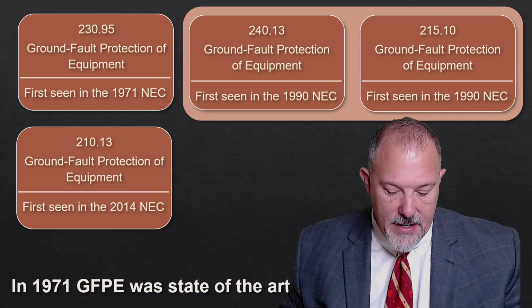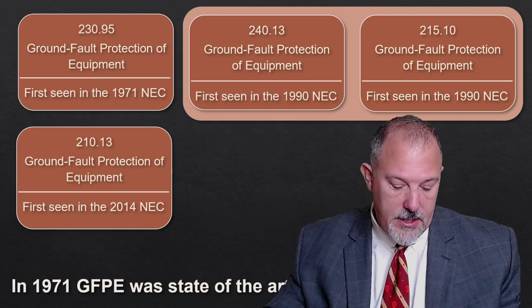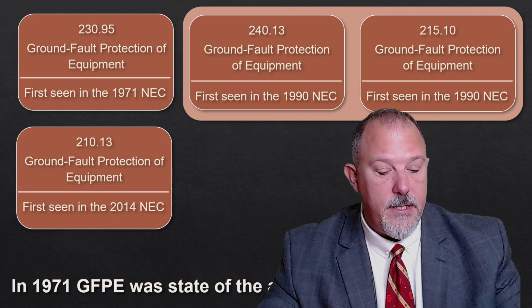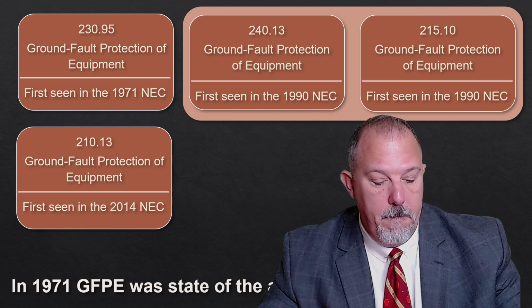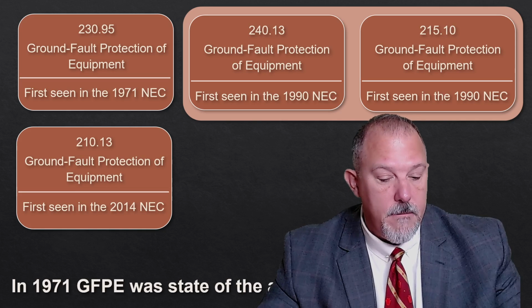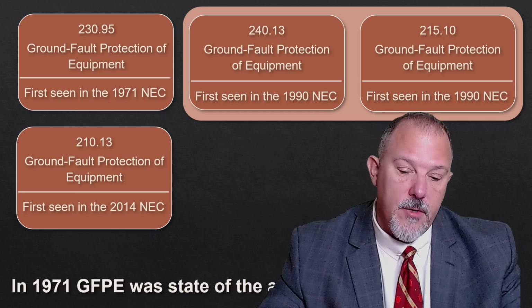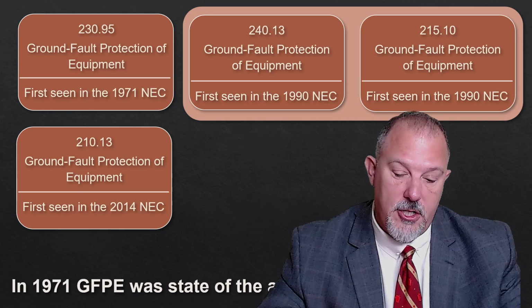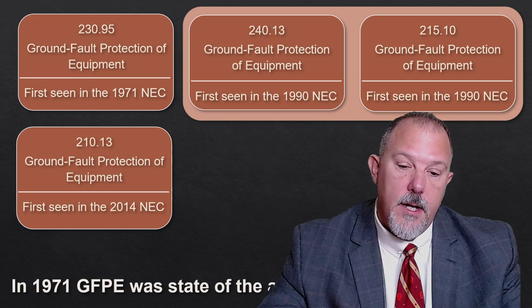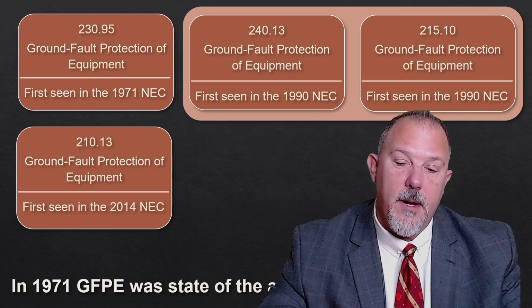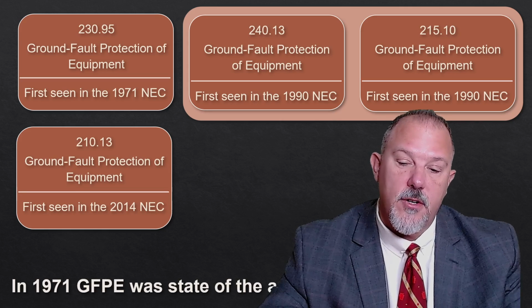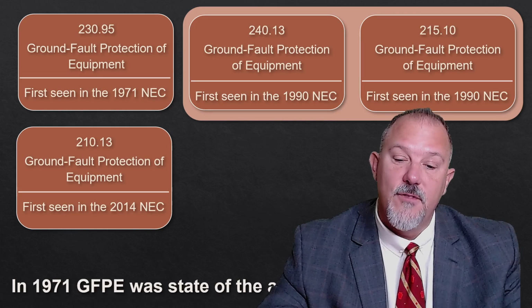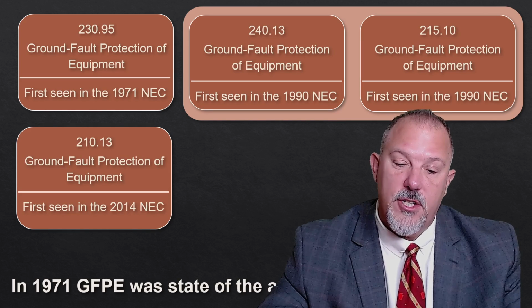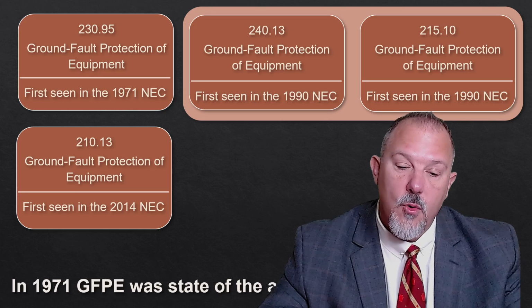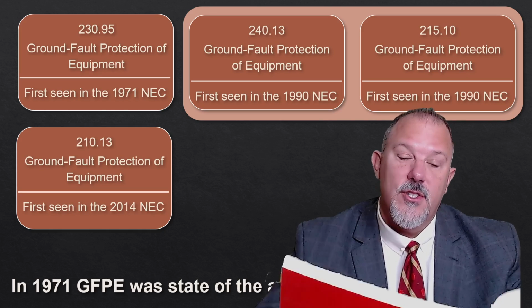Now, if I look at 1971, 230.95 was a new section in the National Electrical Code. I'm just looking at the add a new section, and then there were supporting comments, and then there's a panel recommendation. Ground fault protection of equipment, 1970. Conventional overcurrent protective devices, properly selected in the light of the system's available short circuit current, provide sound equipment protection in the case of normal overloads. Low, high impedance faults, such as arcing to ground, are more prevalent than bolted faults.